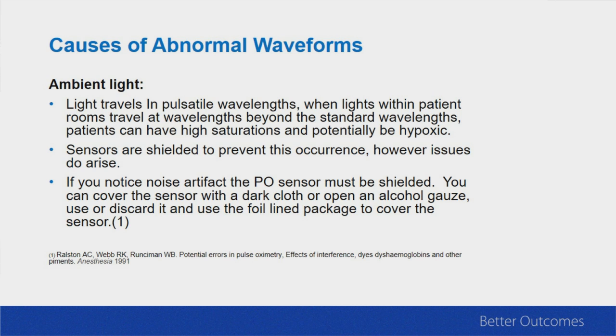So if you notice this noise artifact, remember that real choppy signal on the previous slide, you need to do something to try to shield it. Your pulse ox should be shielded, but there's still some light getting into that. So you can take that pulse ox sensor and literally just cover the hand, if it's on the finger, with a dark cloth. You can bury it under the sheets. Hopefully the patient will keep it there.